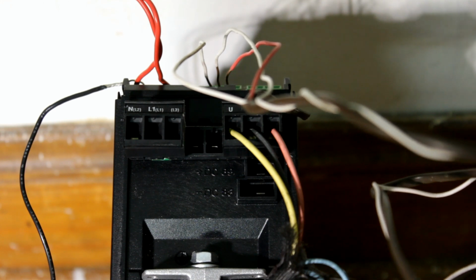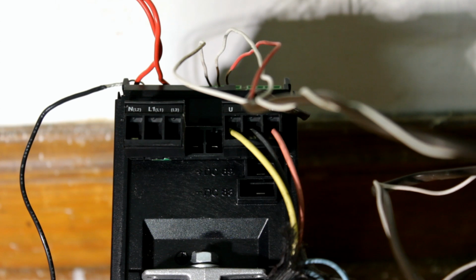But this should make it pretty obvious which VFDs can be powered from DC and which can't, just by the terminals. Now, I know some Toshiba drives had PA, PO, and PB terminals, but the manual will show you what those terminals are for, and those were actually the DC bus terminals. I think PB being the brake, PA being positive, and PO being negative.